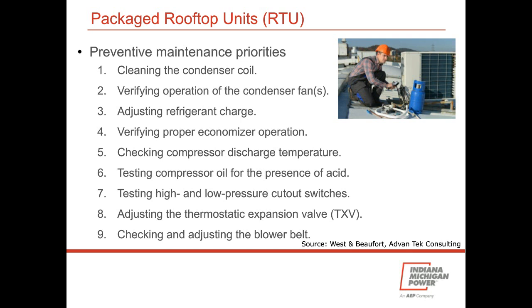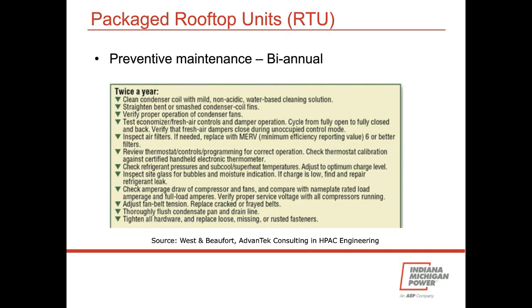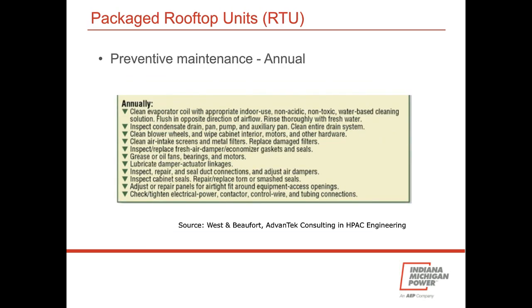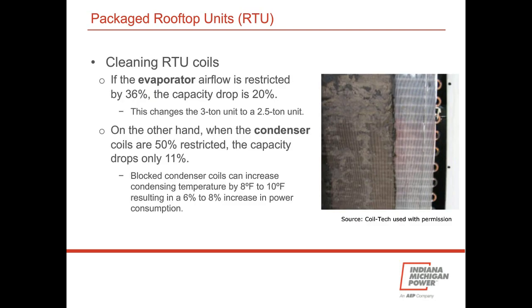Now, if you want to get into more detail, here's a biannual list of things that you can do on your rooftop unit. Things like test the economizer I just mentioned, check refrigerant pressures and subcool and superheat temperatures, check the amperage draw of compressors and fans compared with nameplate, etc. And then here's some things you can do on an annual basis, a little checklist. Clean the evaporator coil, inspect the condensate drain pan, clean blower wheels, etc. And so I'll leave that for you. It's something I think is very useful you can incorporate into your own program.